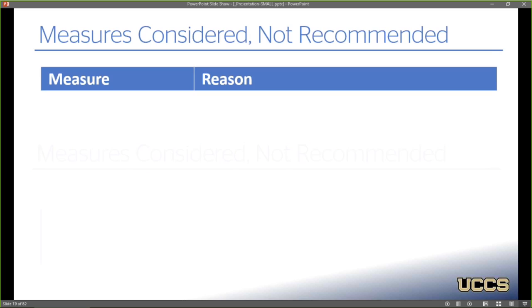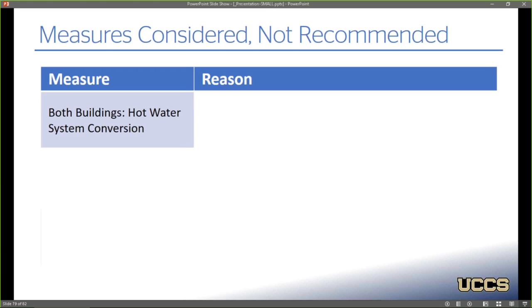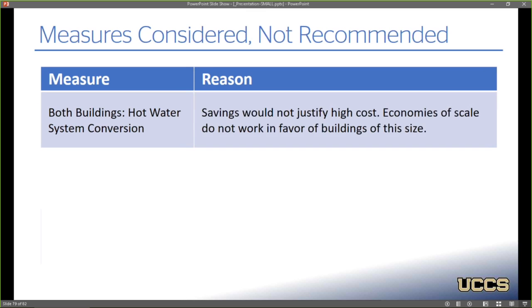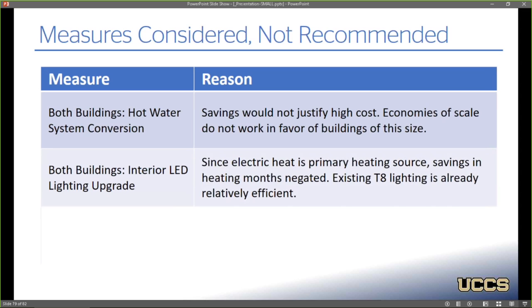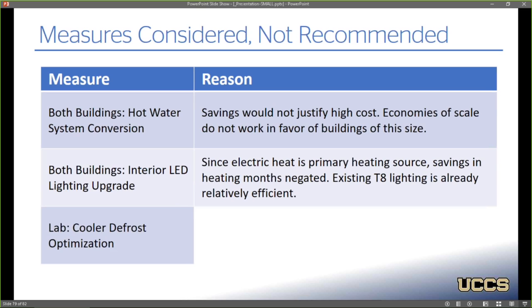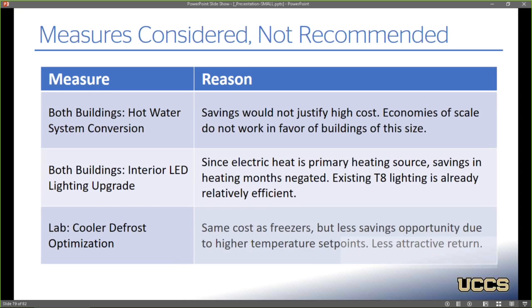So some additional measures that were considered but not performed. Looked at a hot water system conversion for the electric reheat system. The savings here wouldn't justify the cost. These aren't very large buildings, and so the economies of scale just don't work in our favor. Interior LED lighting upgrade wouldn't work very well because electric heat is the primary heating source here, so savings in the heating months are essentially negated, and existing T8 lighting is already relatively efficient. The defrost optimization module could be installed on the coolers, but because they maintain a higher set point, the return wouldn't be as attractive.